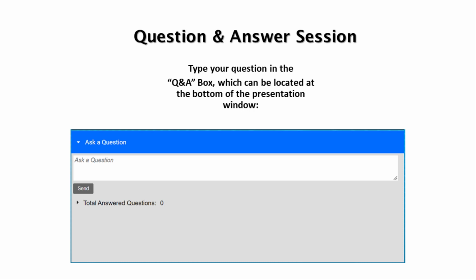Perfect, thanks. If I move a method which uses fully porous packings to superficially porous packings, can I just change the column or do adjustments need to be made? In that case, I would recommend, sometimes you can use faster flow rates with superficially porous particle columns. You could run it just as written, but if you really want to get the true benefit of that superficially porous particle column, then I would recommend increasing the flow rate and then also doing the verification and making sure the system suitability is met.